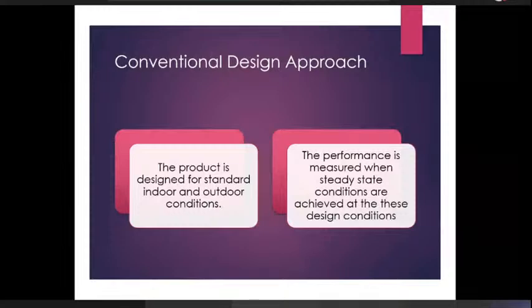There were manufacturers who had designed their product with 1.5 ton minus 10% as their design condition. And they were expecting to benefit from the lower cost, which would lead to a lower price and therefore high volume. And there was no standard. There was no challenge testing regime. So it could be that if you were buying an air conditioner in the period 1999 to 2006, you would have bought a product which you thought was 1.5 ton cooling capacity, but it was giving you maybe 1.3 tons.